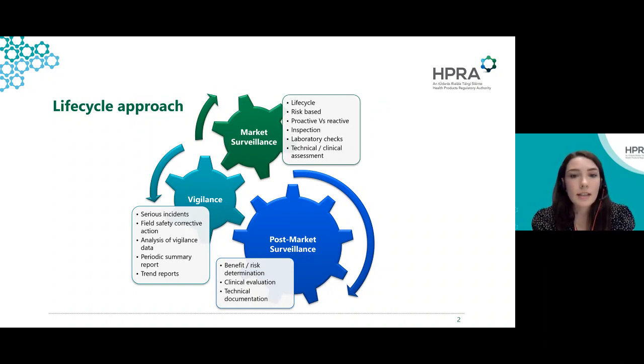So vigilance then, it's the system of notification and evaluation of serious incidents and field safety corrective actions. And finally, market surveillance, which refers to the activities taken by the competent authority in monitoring devices on the market to review their compliance with the medical device legislation. Competent authorities may undertake proactive and reactive work, inspections in manufacturing facilities, or desk-based technical or clinical assessments.